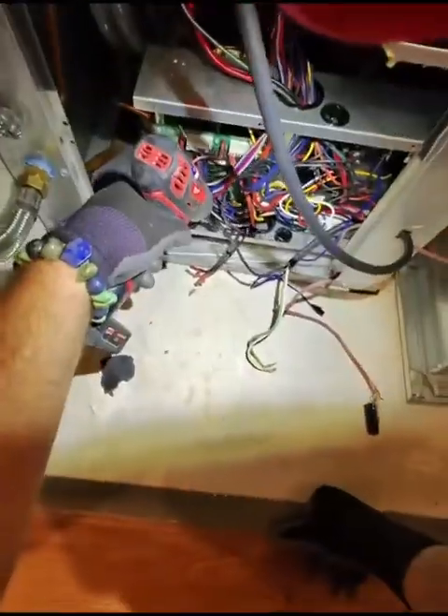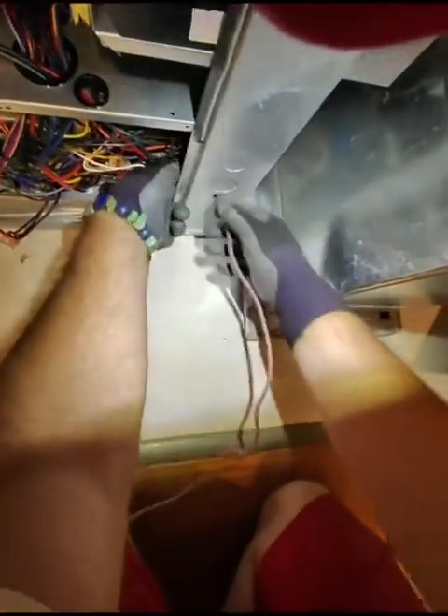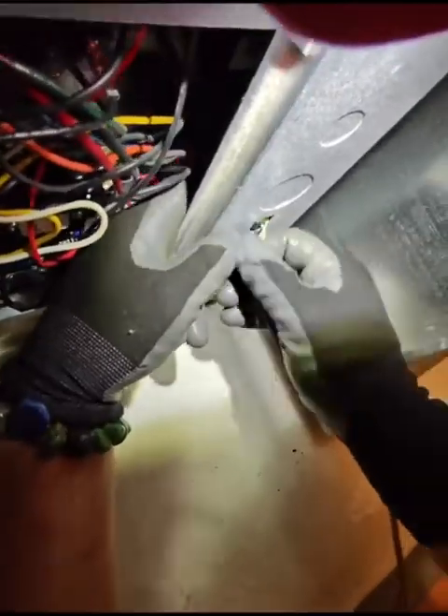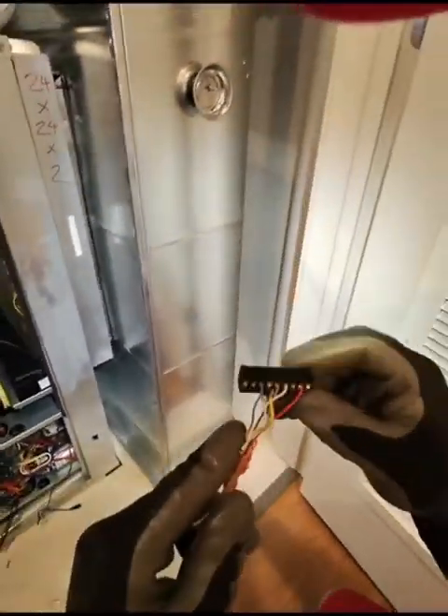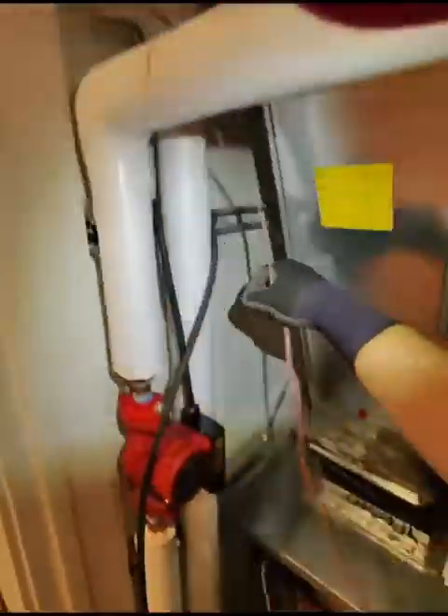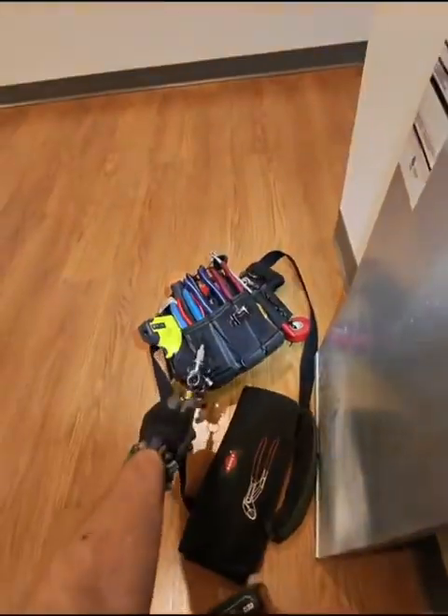Now disconnected the ground wires for the water pump, and then they have a power wire. The neutral seems to go right in with the ground, screwed in with the ground. And then the power wire to the water pump was on the outgoing side of the contactor. As I pulled the thermostat wires through the hole, the yellow one came disconnected, which I have an idea of where it goes, but you can always remove the thermostat and make sure your wiring matches in the back of the thermostat.